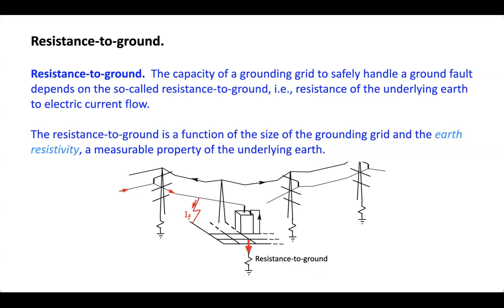So the engineers that design the grounding system have to make sure the grounding system is capable of a couple of things. It must be robust enough to handle the maximum amount of conceivable electric current that needs to be dissipated into the ground. And then they also need to assure the operator that no one will get electrocuted in such a situation. And so you have to build a big grid to get rid of a lot of electric current. And the bottleneck is the resistance to ground. The capacity of a grounding grid to safely handle current depends on the resistance to ground, and the resistance to ground is a function of the grid size and the earth resistivity, which is a measurable property.